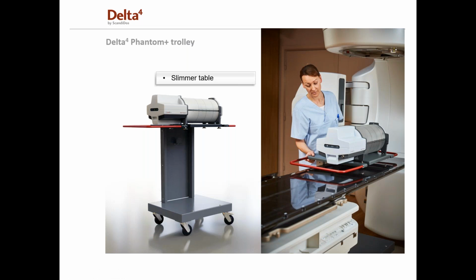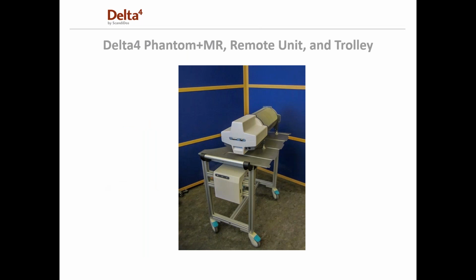This is a trolley that we use on our standard Phantom. It's been around for years. You can see the feet here protrude below the platform of the trolley. So the trolley slides up to the couch. You raise the couch to take the weight of the Phantom off of the trolley and slide the trolley out of the way. And that's all there is to positioning it on the couch.